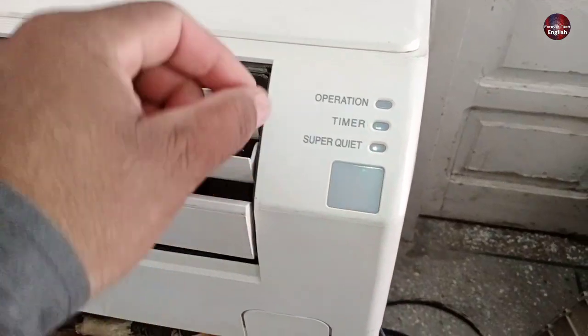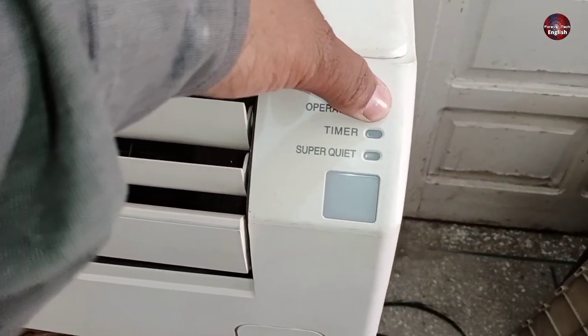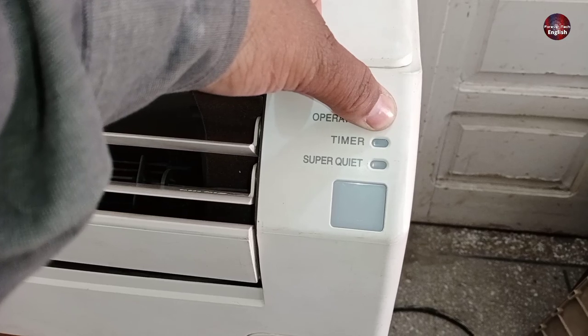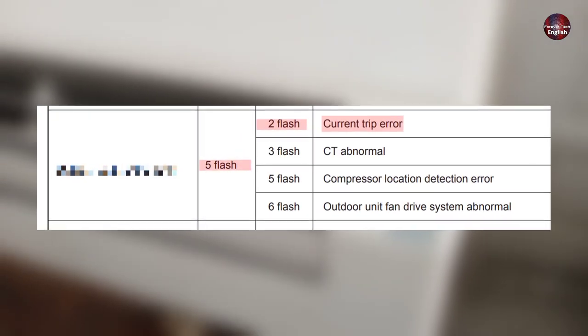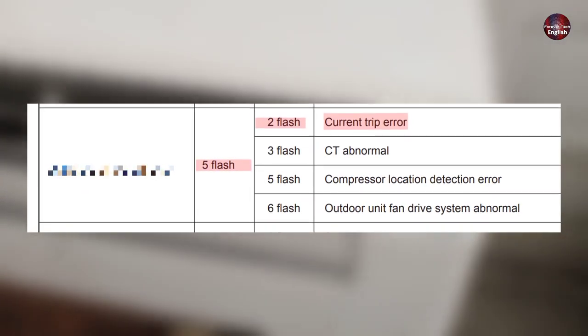Now let's check the timer light blinking: 1, 2 times. The combination of the error is 5 and 2. This is a current trip error.